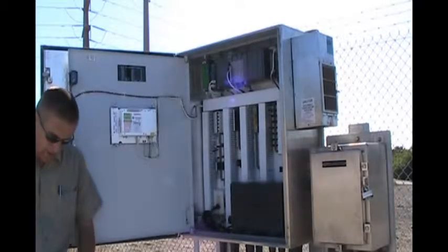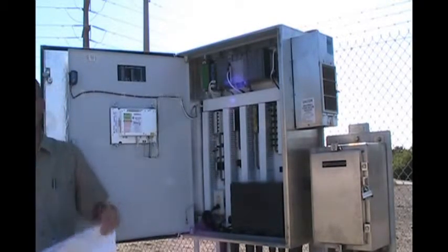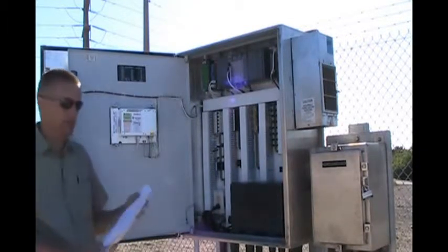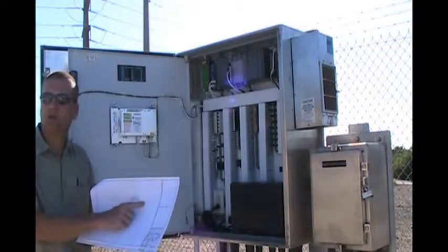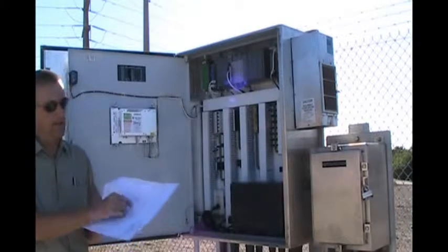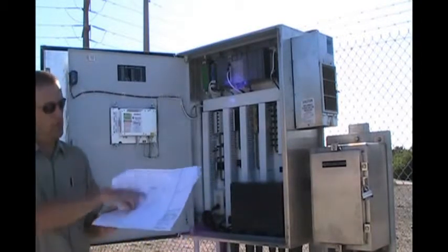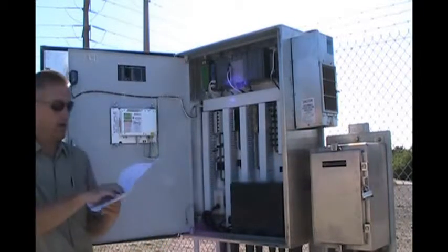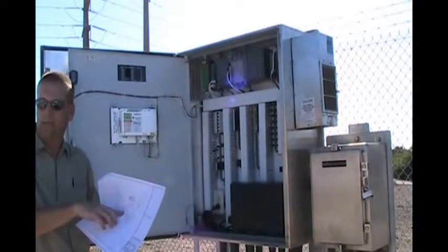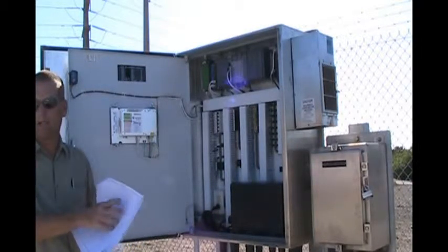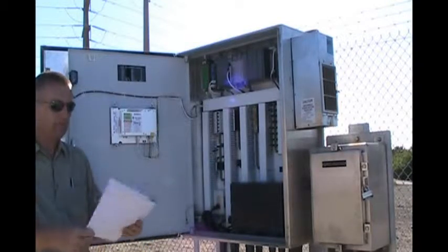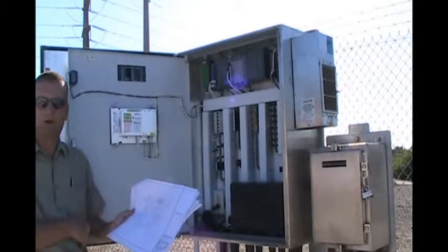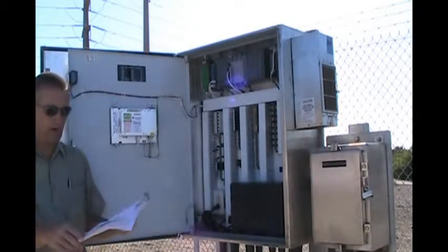Okay, on the next drawings is the F section, which is the communication, the radio from here to RP1. And there's a little diagram giving you the radio's IP address, its gateway, and its subnet. And then on the left is the actual PLC CPU. And under that, I've given you the PLC's IP and the HMI or the OIT's IP, which is the same subnet and gateway as the radio. So I only put the IP address of both. And it gives you a drawing of the components and from here to RP1 for the radio signal.